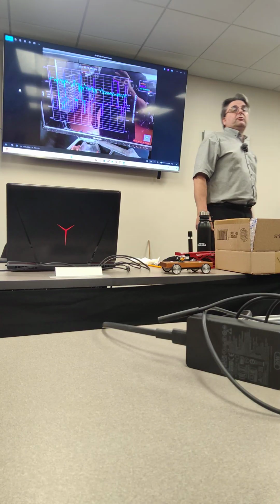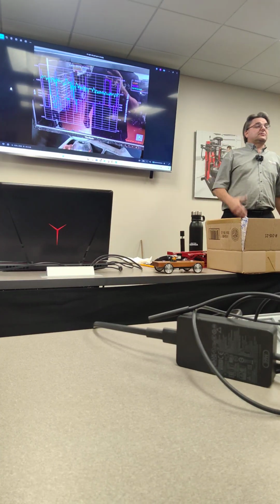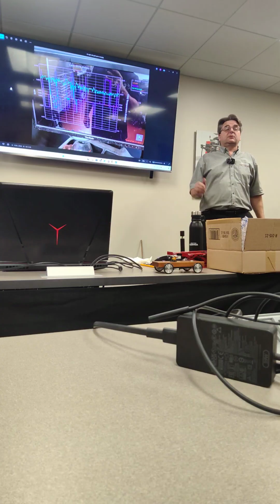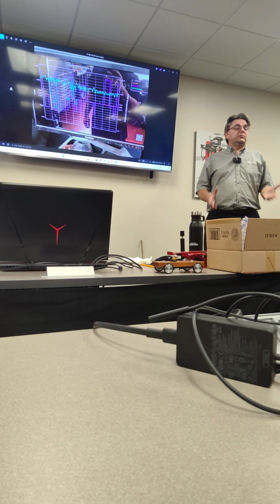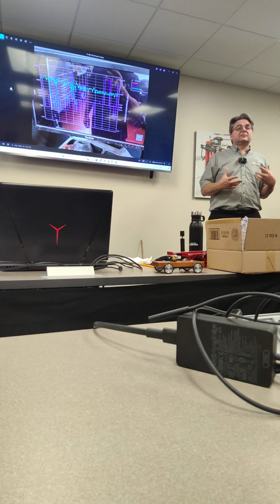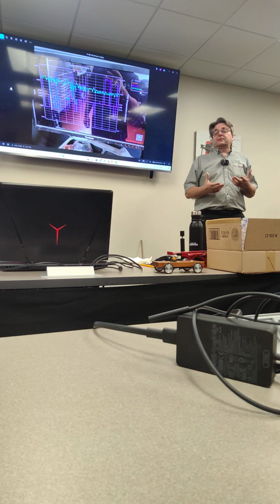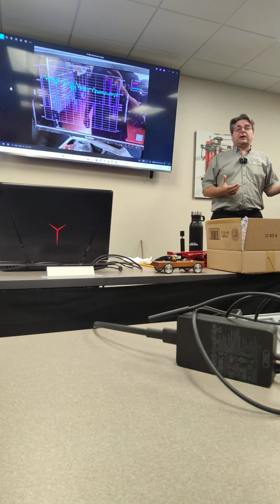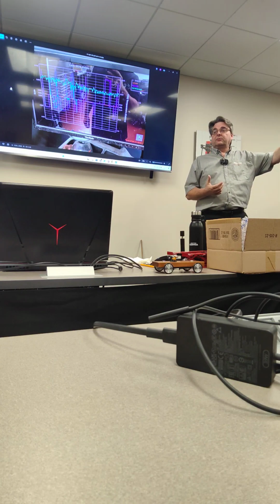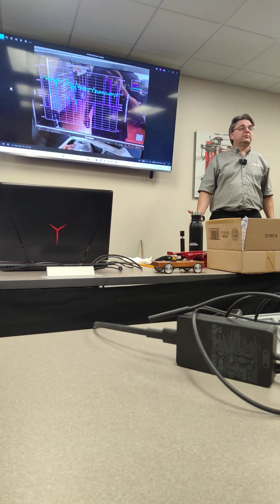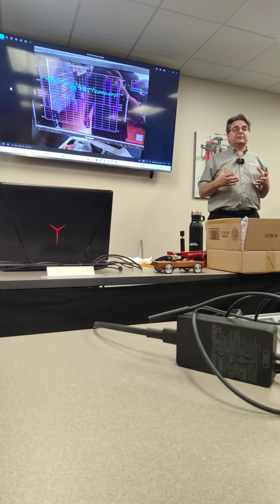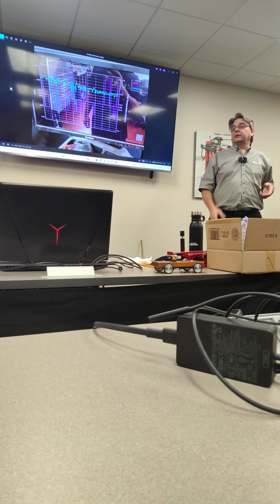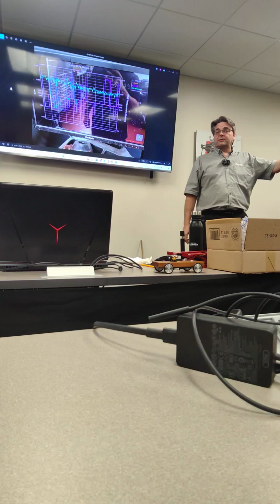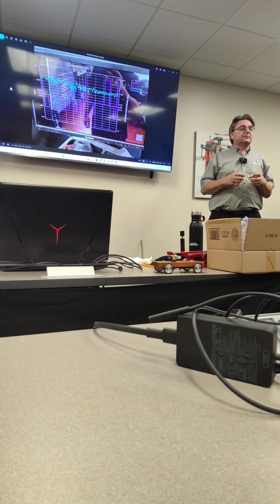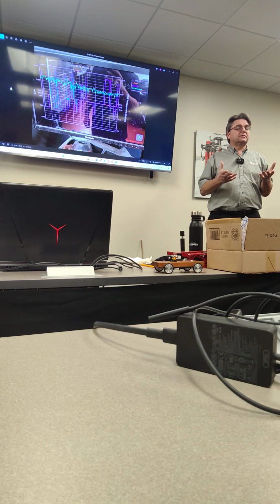Rather than once a week, they wanted to be able to say that our balancers are so advanced and so amazing and so awesome that you didn't have to calibrate our balancers but once a month. So they turned their eyes to the one thing that could affect the calibration, right? If you calibrate it in the morning and it was 18 degrees in the morning and then it's 55 degrees in the afternoon, the balancer tub is going to expand incrementally, right? You won't be able to measure it. It's probably thousandths of an inch, but the balancer expands so that there's less force on the force transducer, so it affects it just a little bit.